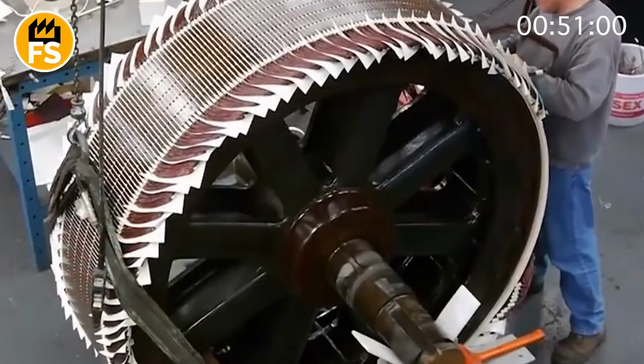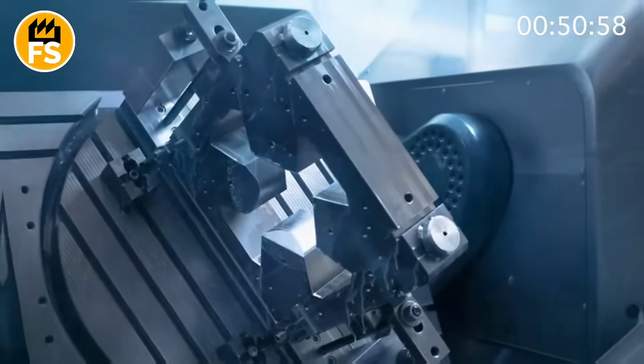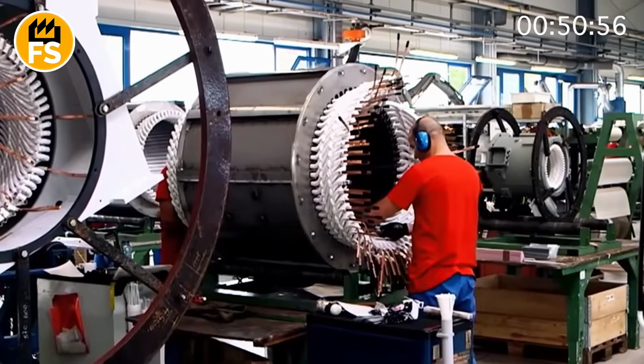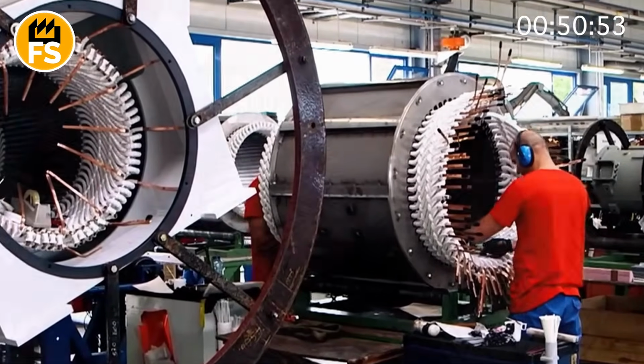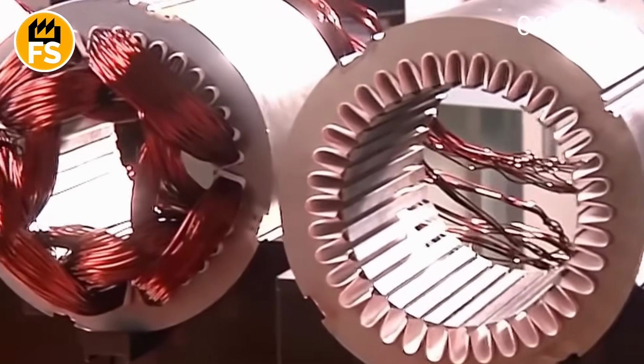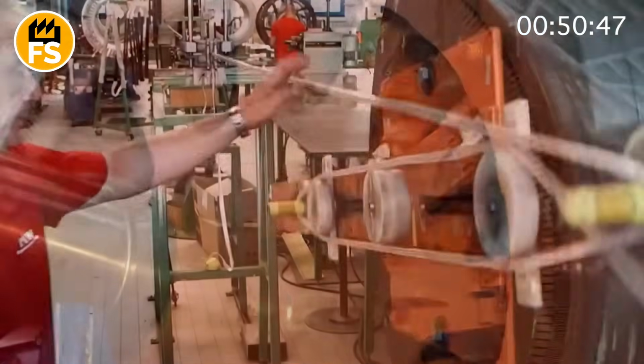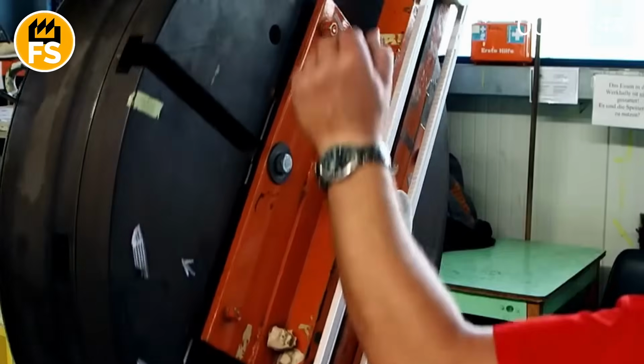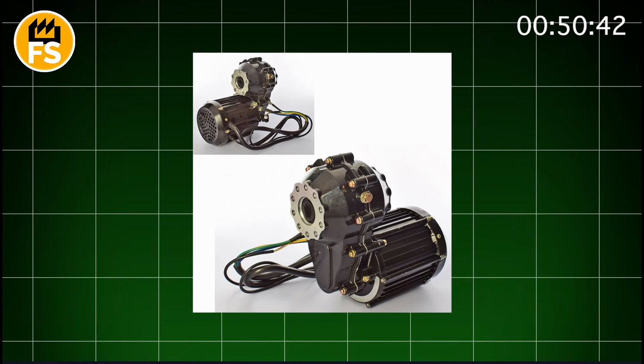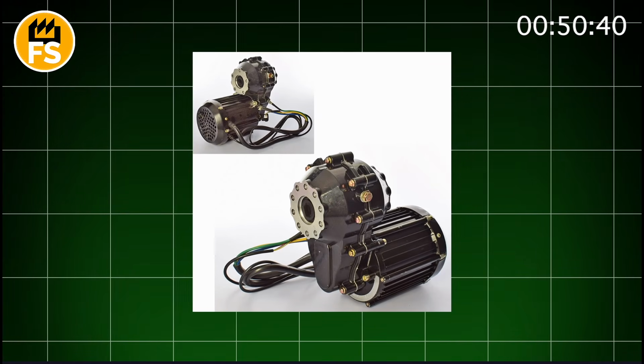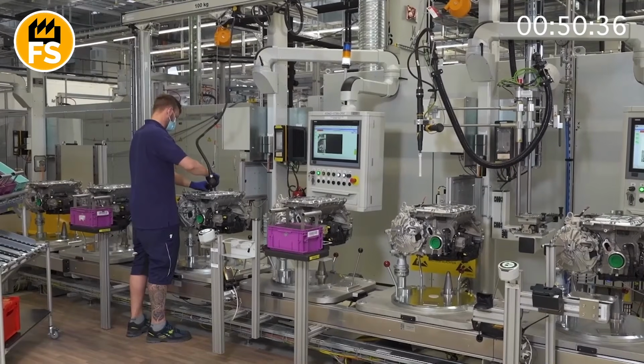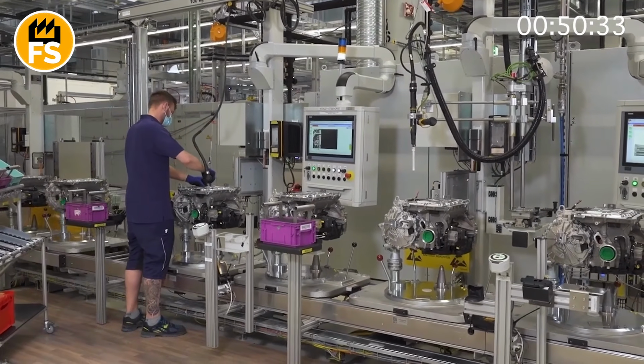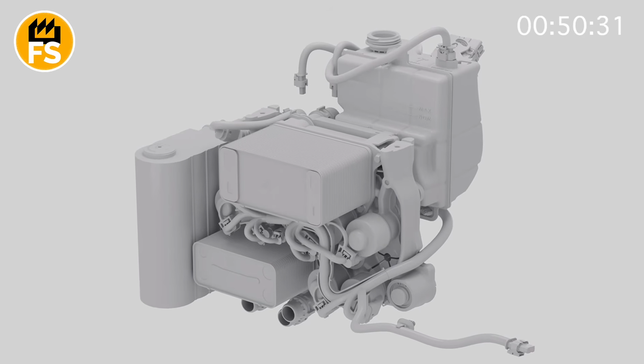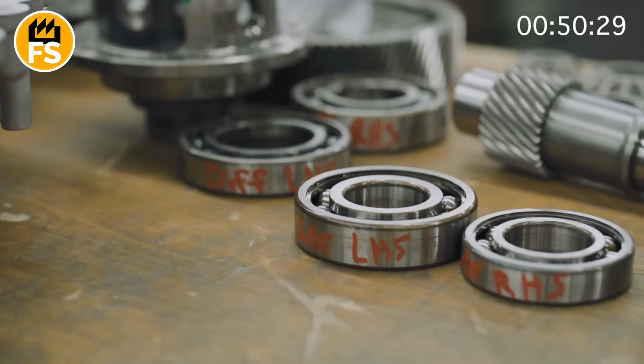The ends of the stator and, if necessary, rotor windings are led out to the terminal box. Here they will be connected in the required circuit, star, delta, or another. In complex motors, temperature sensors are installed to detect overheating before a failure occurs. The motor is now assembled, stator and rotor in the housing, wires connected, bearings in place. But it's too early to start it. First, varnishing, drying, balancing, and testing. All like a ritual before the birth of a real machine's heart.